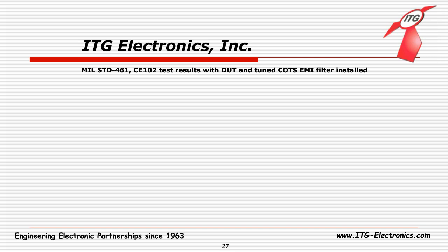As mentioned earlier, it's recommended to have a minimum of 6 dB margin where possible to compensate for production inconsistencies. Now, we always recommend this is the best and most economical path to include an EMI solution into a product, because the cost of incorporating EMI filters increases exponentially as it gets closer to product launch. Incorporating EMI filters at a later date might cause major electromechanical changes in a system that might be ready to ship or is already in production.